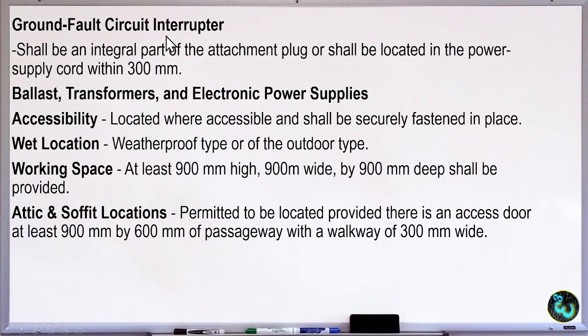Ground fault circuit interrupter. It is required that it shall be an integral part of the attachment plug or shall be located in the power supply cord within 100 mm from the equipment. So part ng ating supply wire or the supply cord, which is within 100 mm from the equipment, shall have a ground fault circuit interrupter.